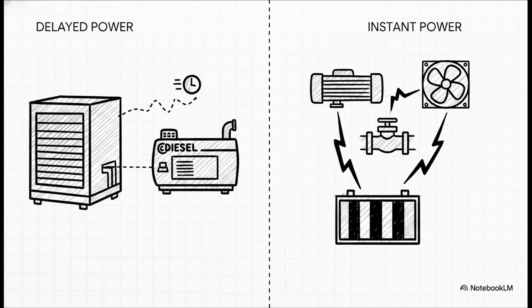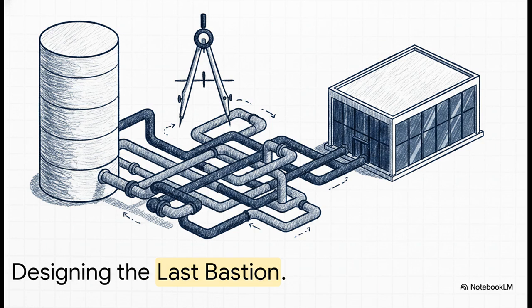That is exactly why the secondary and tertiary chilled water pumps, the motorized valves on the tank, and the CRAH fans blowing the cold air over the servers, they are all hardwired directly to the UPS, the uninterruptible power supply. That battery-backed UPS ensures that the very second the power grid fails, these pumps and fans don't skip a single beat. They instantly draw that life-saving cold water from the buffer tank, ensuring absolute continuity of cooling. Section 5. Designing the Last Bastion.